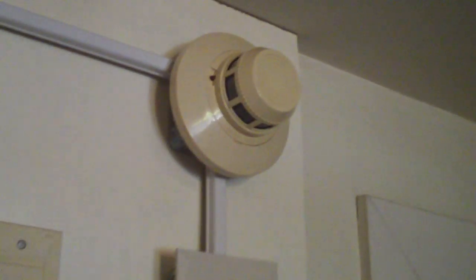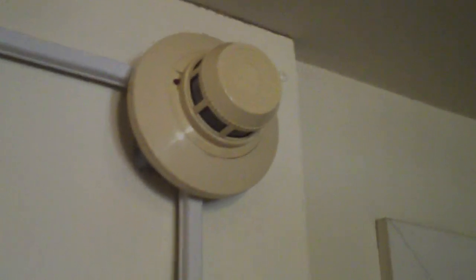This System Sensor smoke detector is still just conventional. Since it's a two-wire smoke, I have to get a special module for it. I also cleared all the troubles in the system. You can see it says system is normal. I usually have my address up there as the banner, but I took that down and just replaced it with the default for this video.